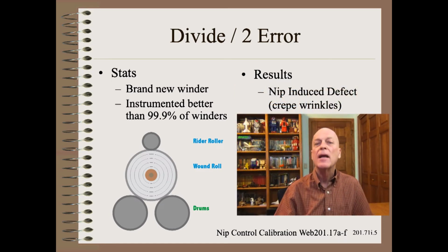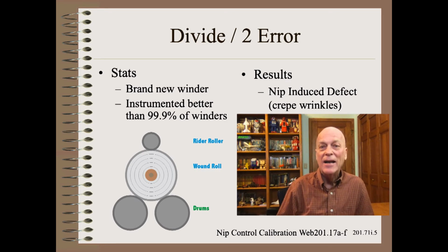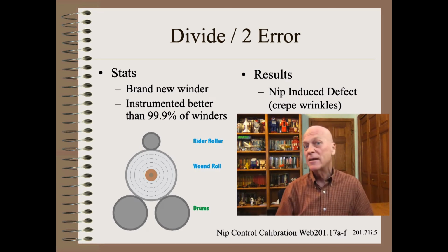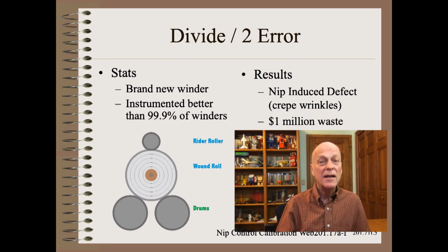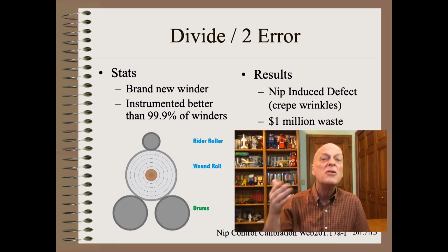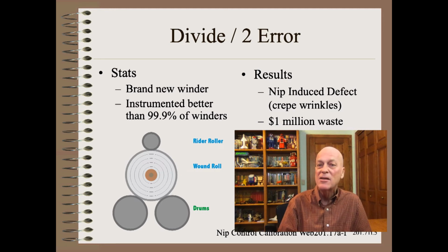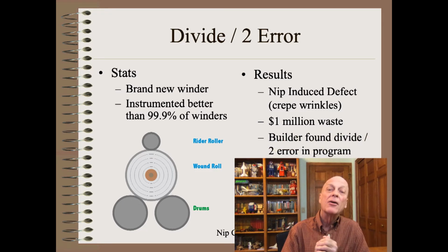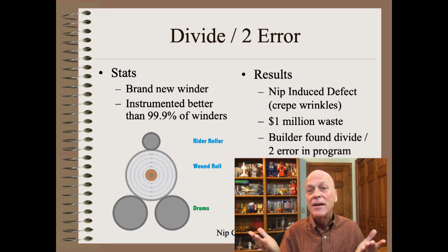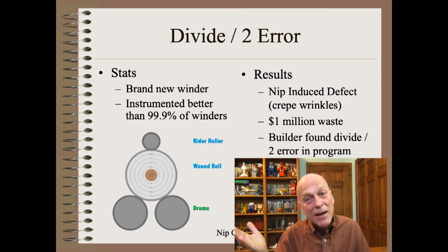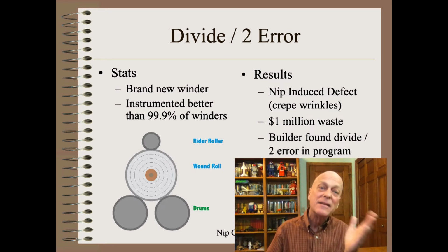In any case, I and other experts were brought in to find out why they were having such a high level of nip-induced defects on this brand new winder. It had cost the mill about $1 million in waste and customer complaints in the first year after startup. After a bit of checking, the senior engineer from the builder, a good friend and colleague, found a divide by 2 error in the PLC program. In other words, the actual nip was twice as high as the program thought.